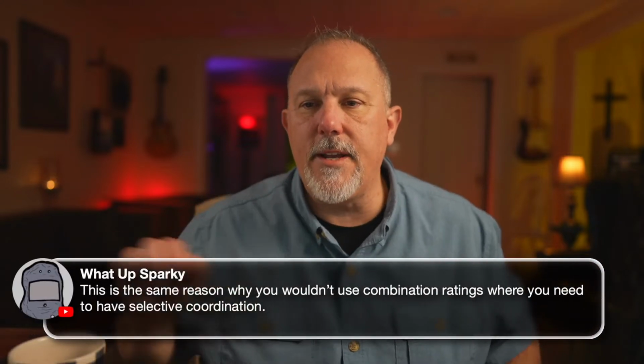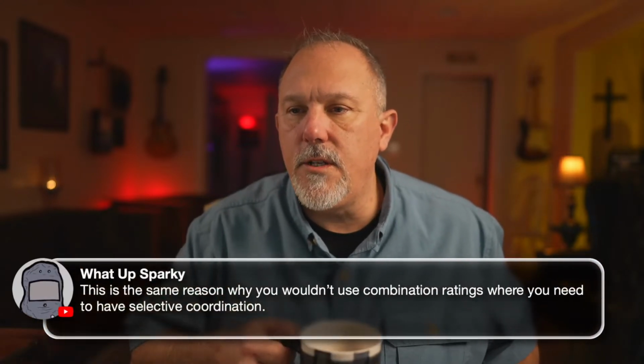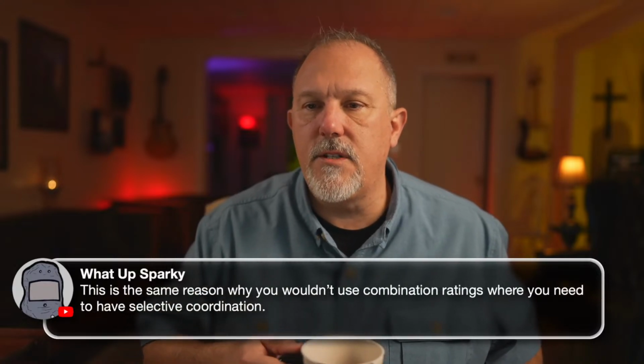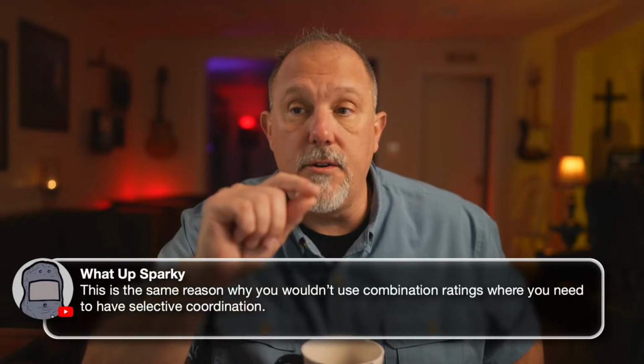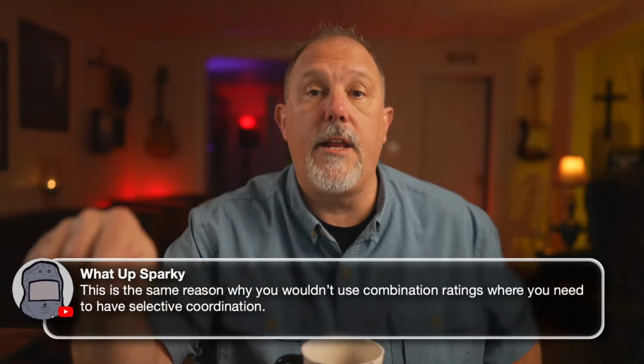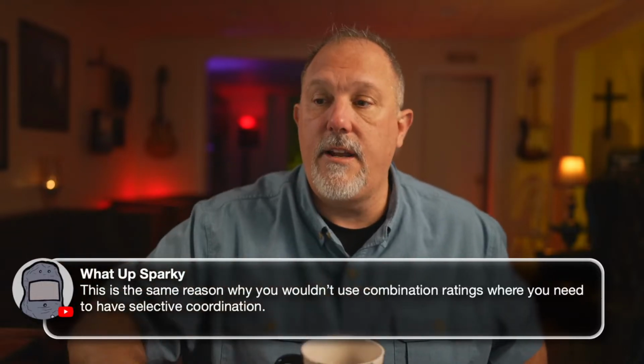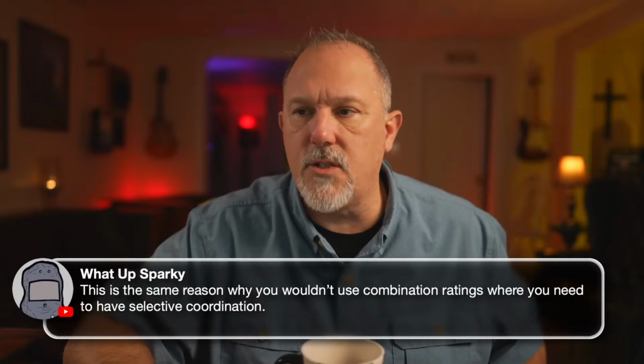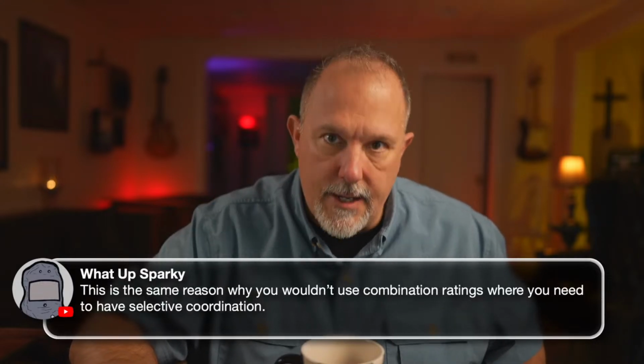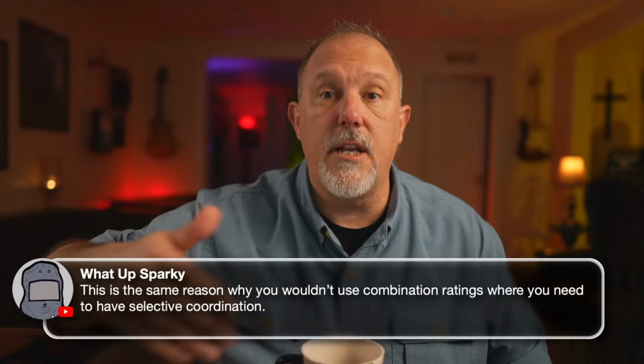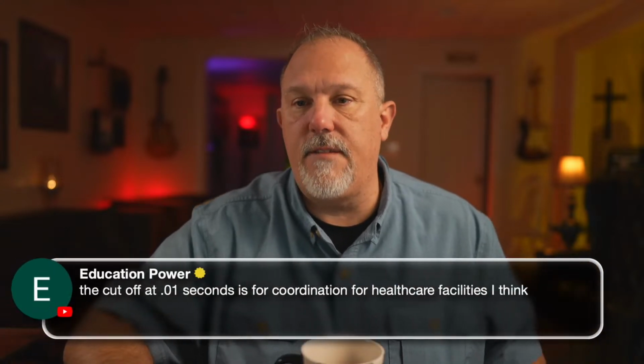Hey, what's up, Sparky? This is the same reason why you wouldn't use combination ratings where you have to selectively coordinate. Yeah, series ratings are... You would not do series ratings in a selectively coordinated environment. I'm assuming that's what you mean by combination ratings. That would be correct, because in series ratings, they're both going to open to clear that fault current.